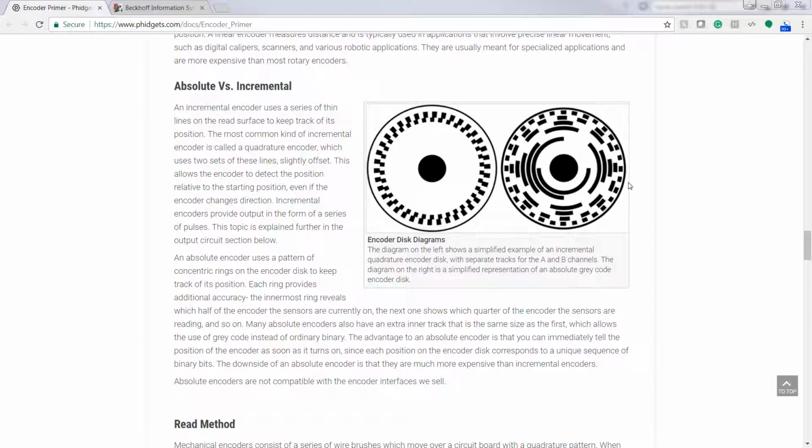But a multi-turn doesn't just encode forever. You typically have mechanical limits where it's going to roll over in a gearing situation like a clock. So what they'll often do, between the motor and the actual servo drive, is put a little battery backup on this encoder. If it is spun by hand, it still counts those pulses with a little battery circuit. There are some problems with that as well, like you have to change the battery every 8 to 10 years or something like that, and potentially when you unhook the cable, you lose that.